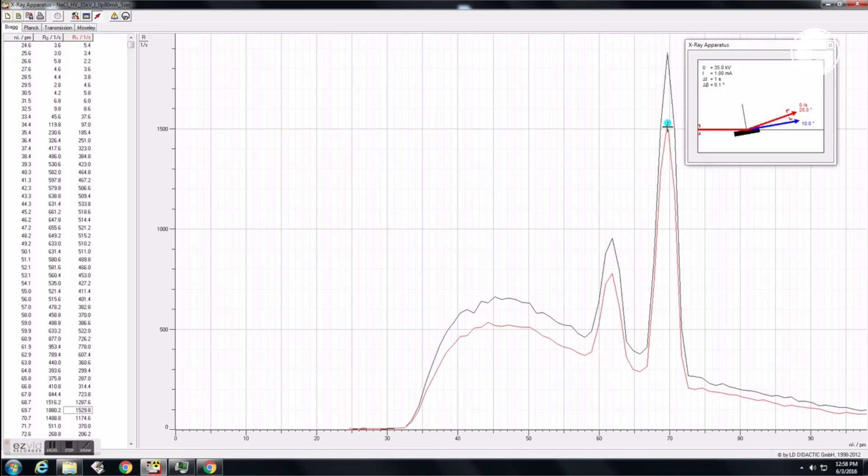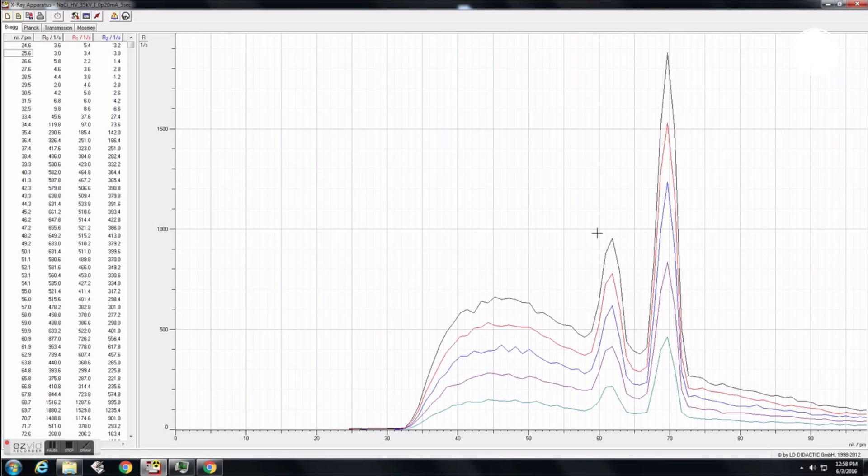Return the tube to 35 kV, and now take data for tube currents of 0.8, 0.6, 0.4, 0.2 mA. The graph here shows the overlay of spectra for all 5 current setups.